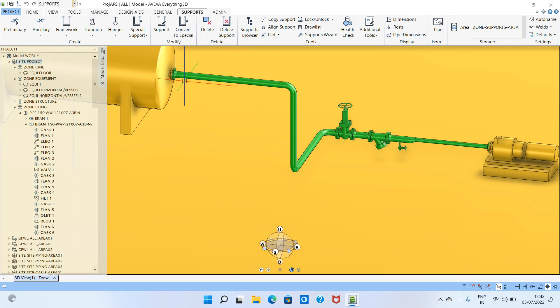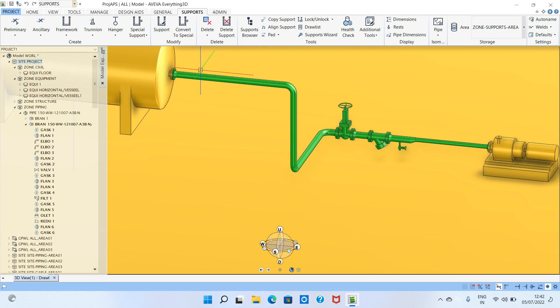For example, imagine this is a waste water system or similar. For that system there are support standards and support procedures. That standard will explain what type of supports you have to model and what the distance is between two supports. The distance in a pipe rack is different from a sleeper, and also different for above ground, underground, or buried pipe.